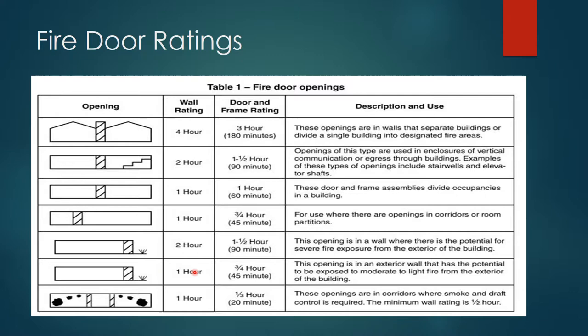A 2-hour wall with 90-minute rating applies when there is potential for severe fire exposure from the exterior of the building — for example, combustible shrubs nearby. Exterior 1-hour walls use a 3/4-hour door when there is a light fire potential. A 1/3-hour or 20-minute door is where smoke and draft control is required, and this is where we get into particularly healthcare corridor doors and egress doors that work two ways.